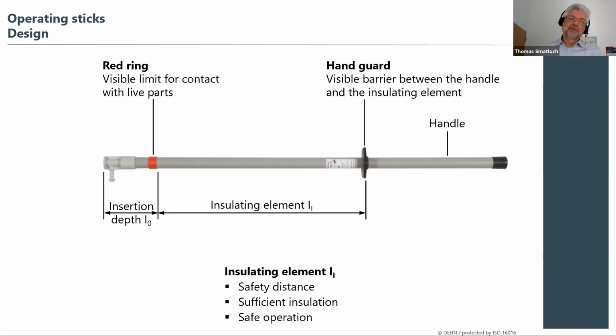And on the left part, you can see this red ring as a visible limit for contact with live parts. So the last part of the tool on the left-hand side is here called insertion depth. That means there should be no live part below this red ring when you go into the equipment. And this piece, of course, depends on the construction of the equipment where it is used, if you have short distances or longer distances. Okay, so later on we will speak about the special clothes for the installer as well.